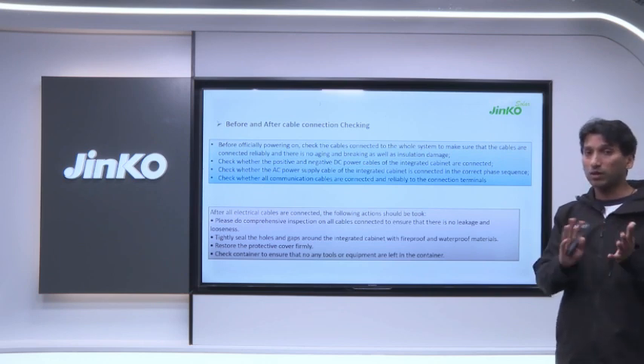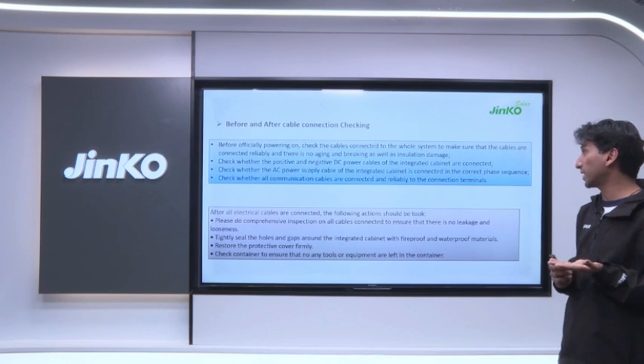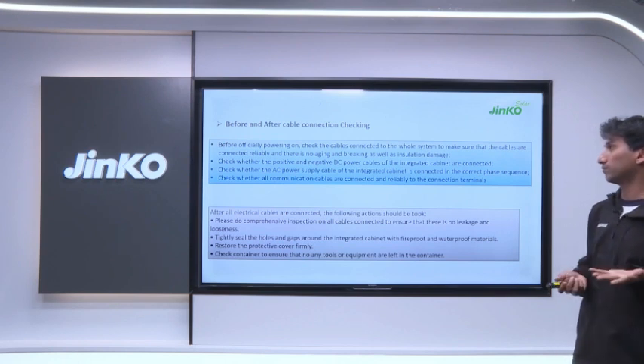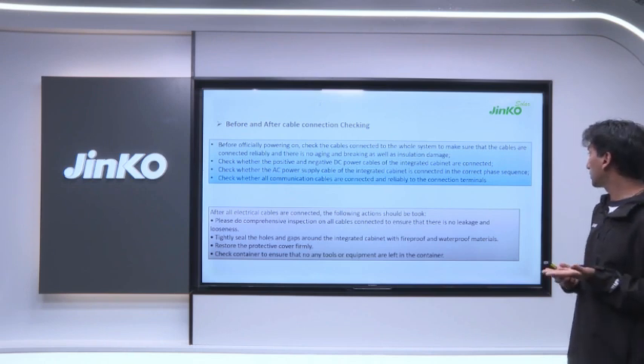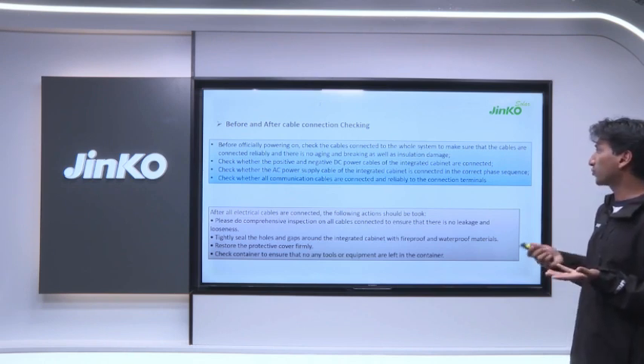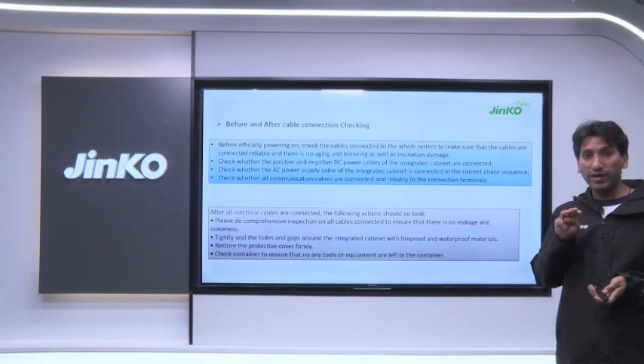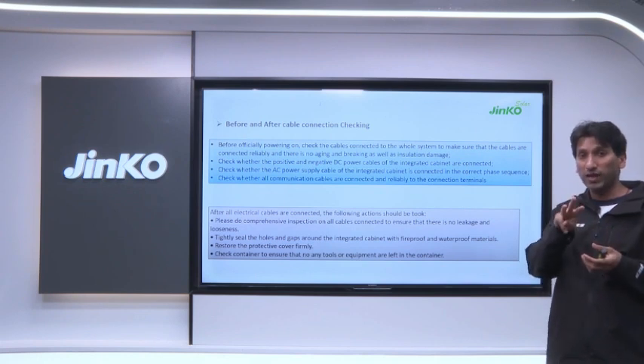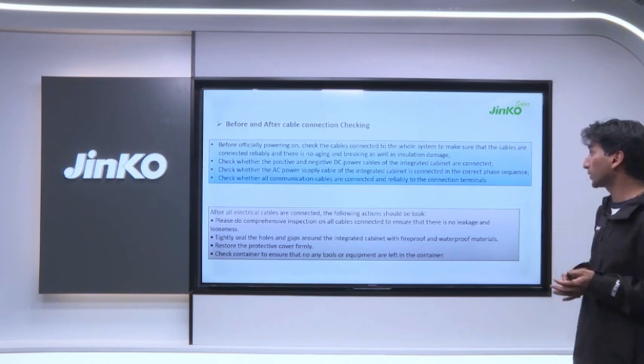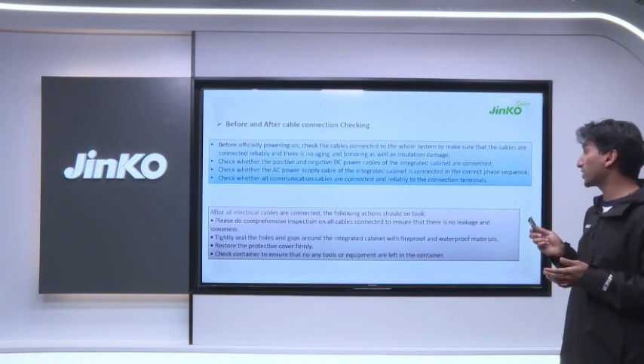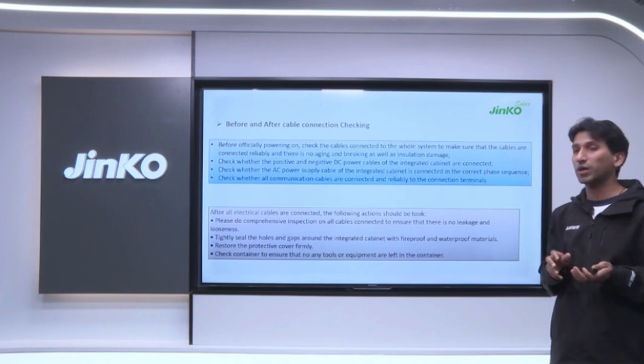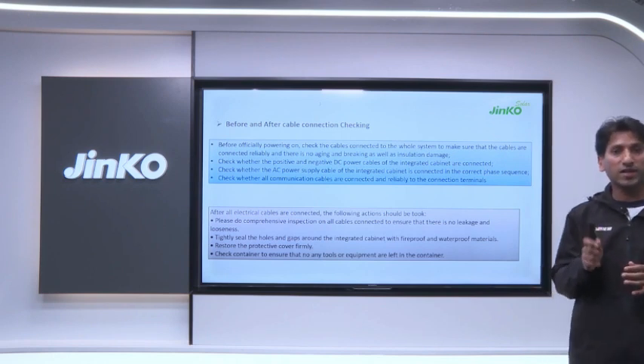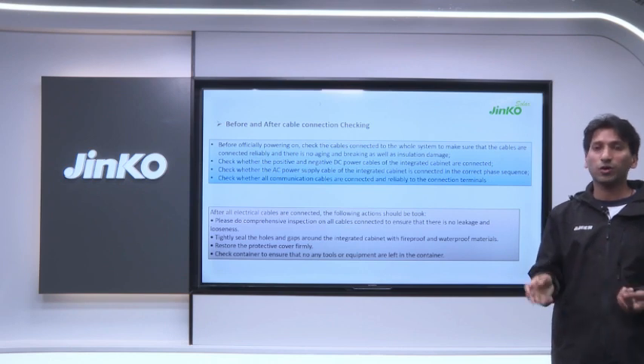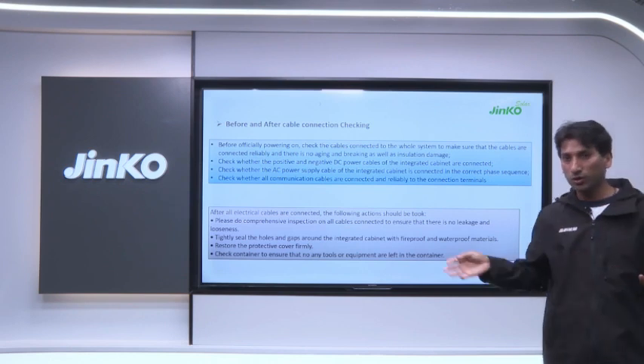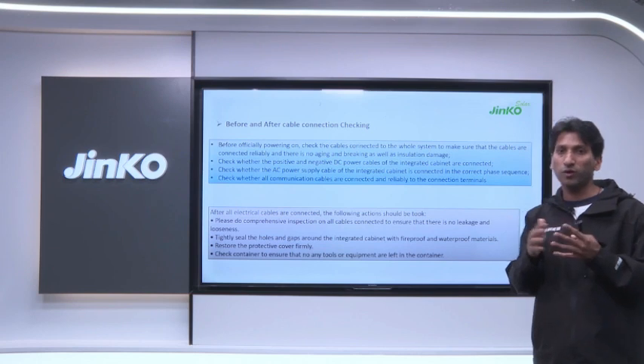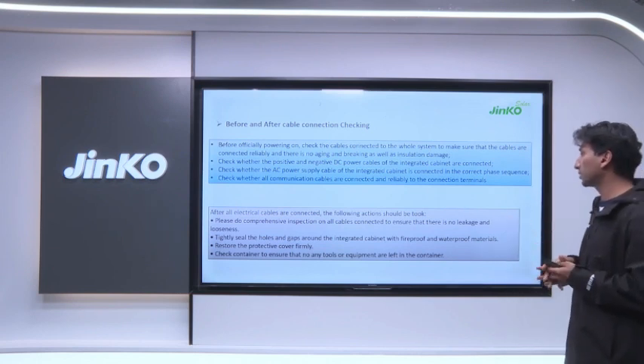It should not be on the wrong poles. That can cause a very big fault. We have to check that the AC power supply that you're connected to is in the right phase. The phase sequence should not be wrong. And we have to check that all the communication cables are connected reliably, because communication cables are also very important. If there is any mistake on the communication cables, the system will not power up, because the communication is controlling all the switching on and off of the contactors inside the system.